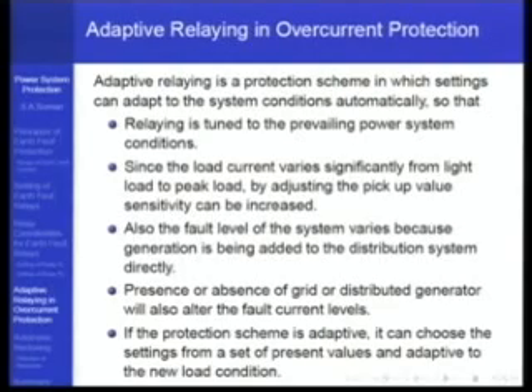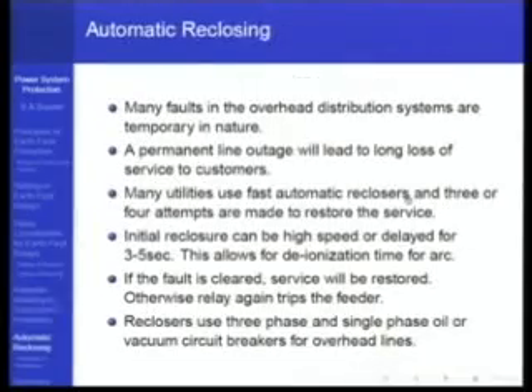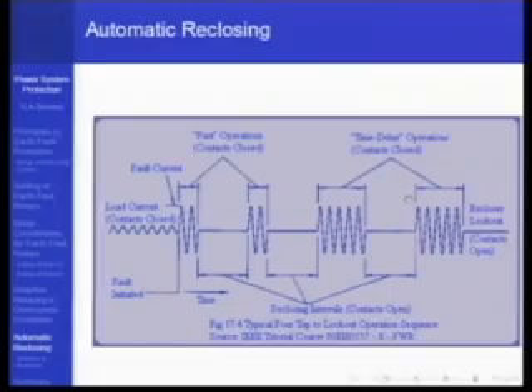So that is a simple idea of adaptive protection in this particular sense, that you don't try to give one setting for all kinds of things. Try to give settings which depend upon which circuits, feeders are in service, or loading conditions, or time of the day, and that can give you a more sensitive protection than one single setting. So that's the notion of adaptive protection.